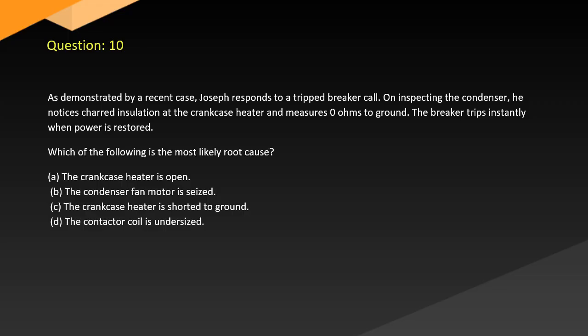Question 10. As demonstrated by a recent case, Joseph responds to a tripped breaker call. On inspecting the condenser, he notices charred insulation at the crankcase heater and measures 0 ohms to ground. The breaker trips instantly when power is restored. Which of the following is the most likely root cause? A. The crankcase heater is open. B. The condenser fan motor is seized. C. The crankcase heater is shorted to ground. D. The contactor coil is undersized.